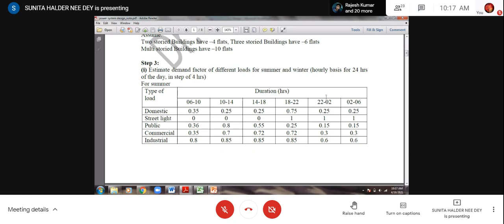But whatever you have taken, you write this table accordingly. But for street light, obviously, if I assume that street light will be switched on at 6 p.m. at night and switched off at 6 a.m. the next morning, then we shall assume that all the street lights are in operating condition. So all will be on from 6 p.m. in the evening to 6 a.m. of the next morning. Demand factor obviously will be one. There is no deviation, and otherwise they will be switched off, so it will be 0. Understood my point?